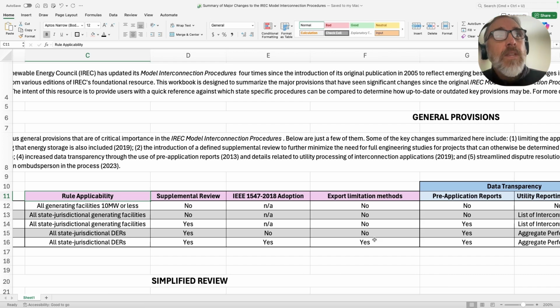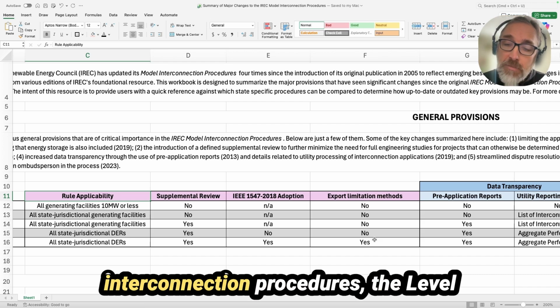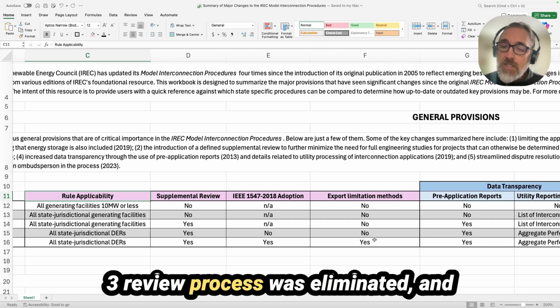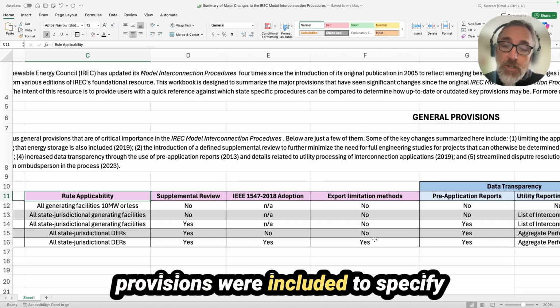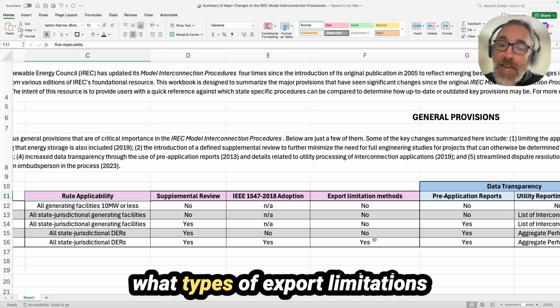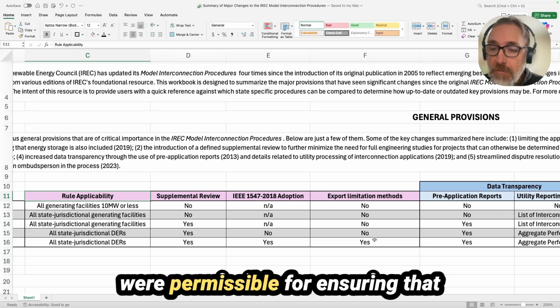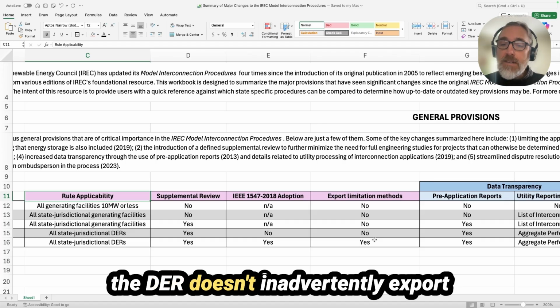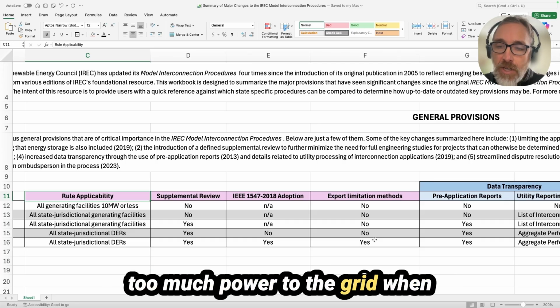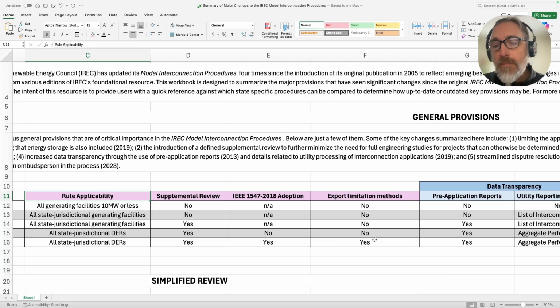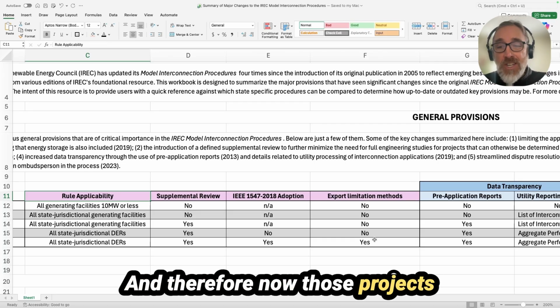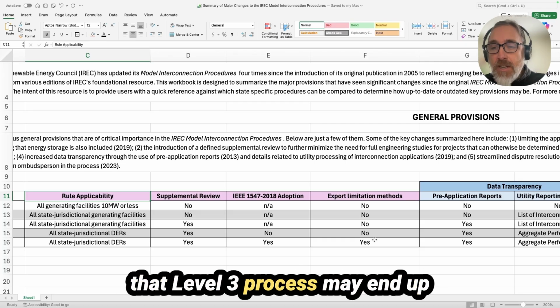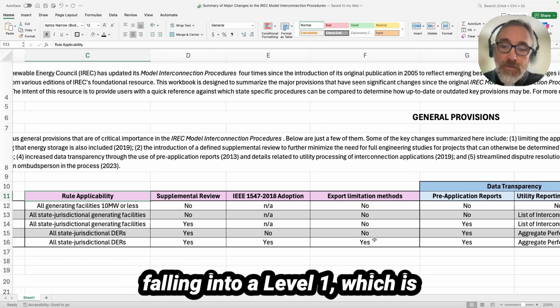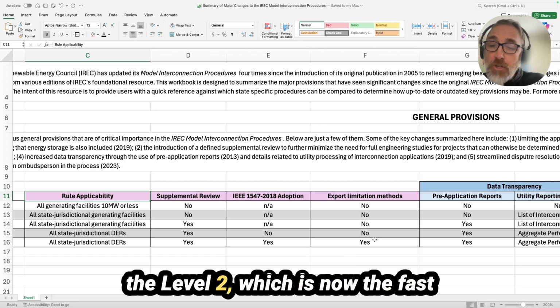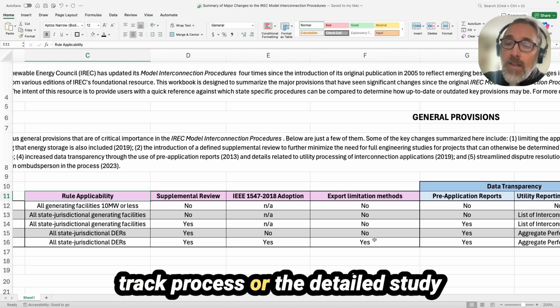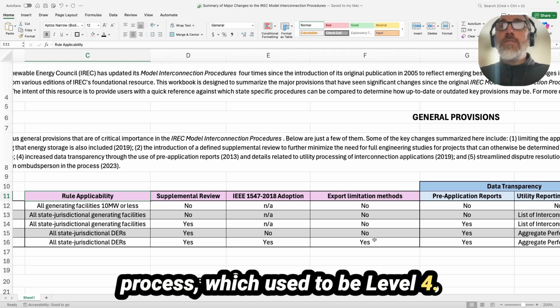So in the 2023 IREC Model Interconnection Procedures, the level 3 review process was eliminated and provisions were included to specify what types of export limitations were permissible for ensuring that the DER doesn't inadvertently export too much power to the grid when it could create issues on the grid. And therefore, now those projects that normally would have been under that level 3 process may end up falling into a level 1, which is now just the simplified process, the level 2, which is now the fast track process, or the detailed study process, which used to be level 4.